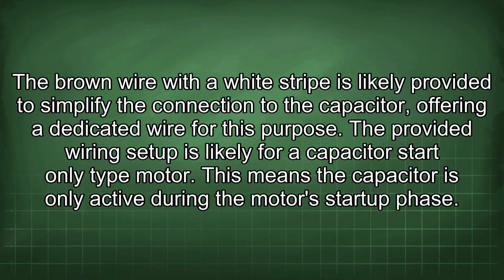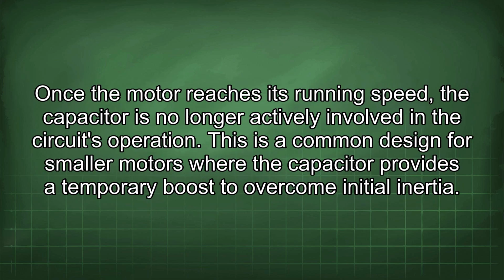This means the capacitor is only active during the motor's startup phase. Once the motor reaches its running speed, the capacitor is no longer actively involved in the circuit's operation. This is a common design for smaller motors where the capacitor provides a temporary boost to overcome initial inertia.